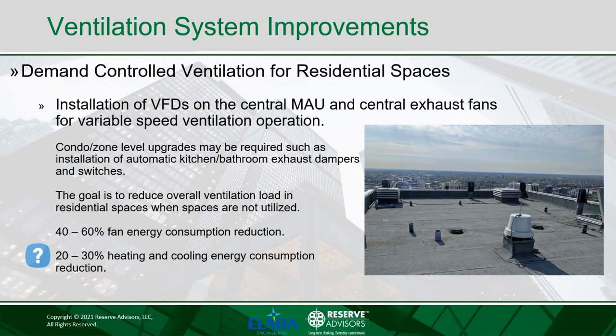So the main benefit of demand control ventilation is that not only are we achieving fan energy savings, but we are also achieving heating and cooling energy consumption savings, which is very critical, because if we are controlling the speed of the exhaust fans, that means we are controlling the amount of air being exhausted, removed from the building. That means we need to bring less fresh air to the building, and we need to air condition less air introduced to the building. So that's a significant part of this project.